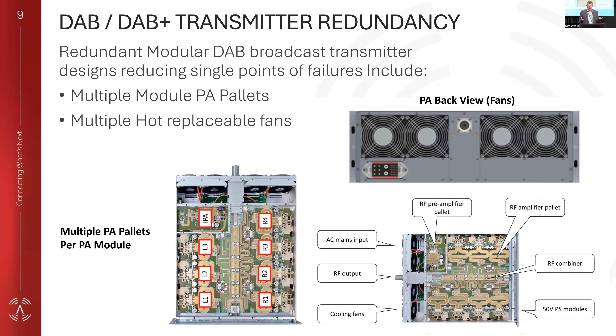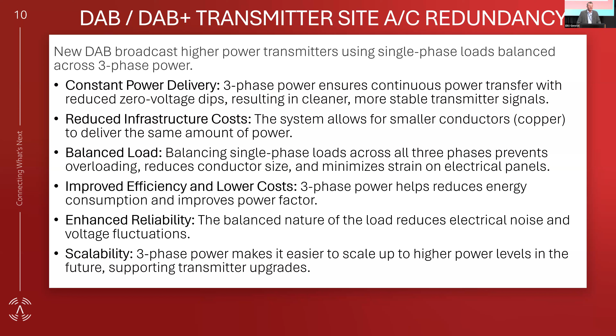AC redundancy - if you have a higher power transmitter, it's very recommended to use a 3-phase connection. If you have a medium power transmitter, 3 phases also have an advantage because they address different components in the transmitter, giving you a better load, a cleaner electrical system, a better load factor. The infrastructure cost matters too - the wiring for single phase versus 3-phase is different, and the circuit breakers are different. But the important thing is enhanced reliability and scalability, because a 3-phase system generally allows you to be more flexible in how you run it. I know some sites are single phase only, so depending on the site, you may have limitations in how to deploy that.